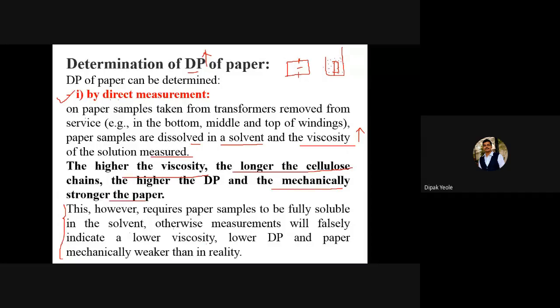Sorry, dissolved is not the correct word, fully soluble is the correct word. Because if we are taking it partially in air and partially in solvent, then it will indicate a false reading, or sometimes indicate lower viscosity. Obviously that is a direct relation: if lower viscosity is available, the cellulose chain is poorer, which results in lower DP, and we know that with lower DP, the paper is mechanically weaker than in reality.